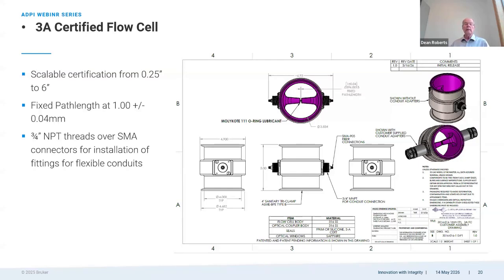It's very symmetric, and we've got 3/4 inch NPT fittings on the SMA connectors for the fiber optics, which allow you to put a flexible conduit fitting on to protect the fiber from washdown and any sanitary processes going on in the plant. That flexible conduit would then go into a junction box where it transitions to a rigid conduit to protect the fiber. Next slide.